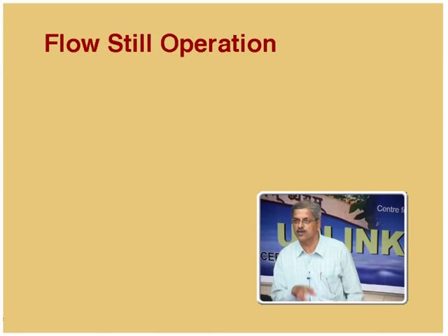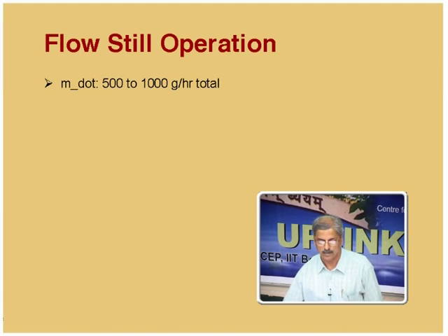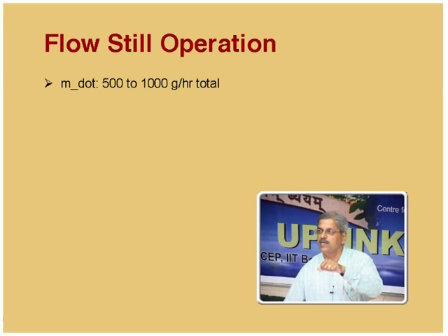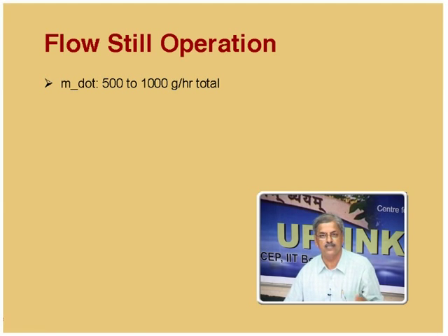This complete design is made in glass rather than metal. Mass flow rates in the range of 500 to 1000 grams per hour can be handled. If one goes beyond this for the actual design given, there will not be enough time for mass transfer to occur and the vapor and liquid obtained will not be in equilibrium. So to be safe, the design should not exceed these flow rates.